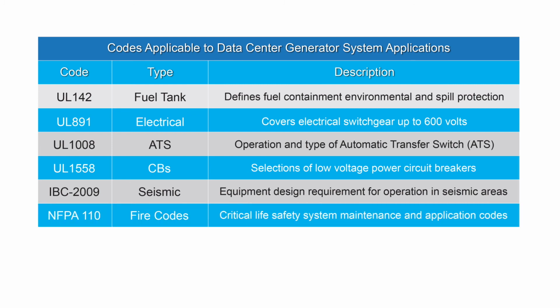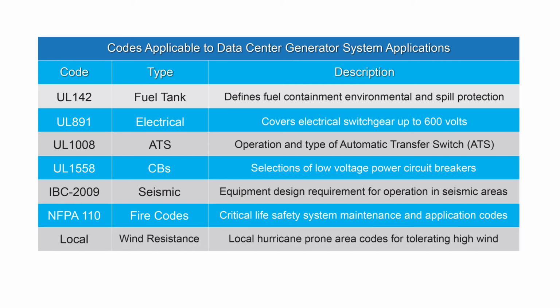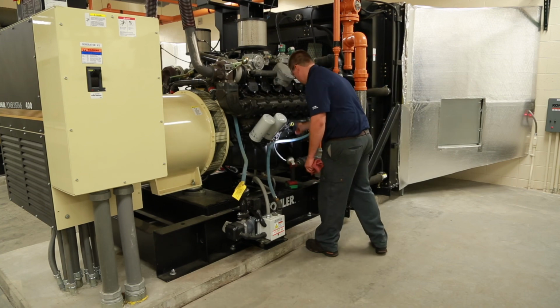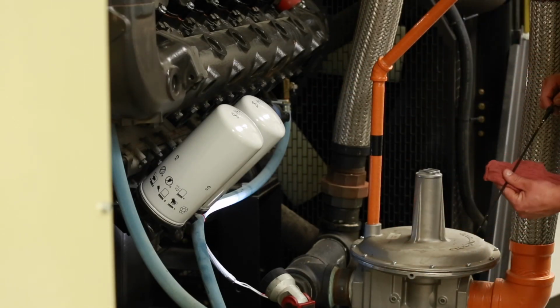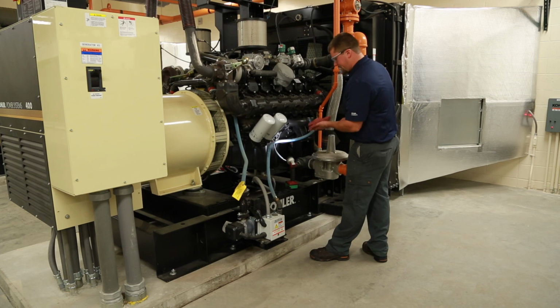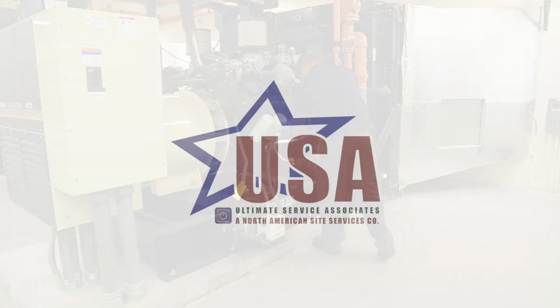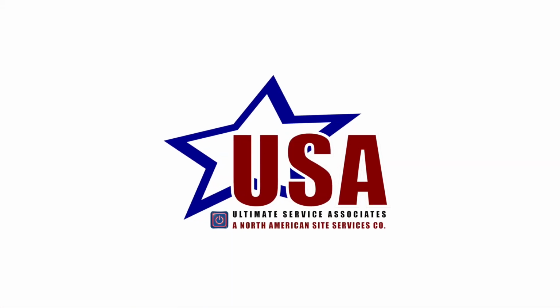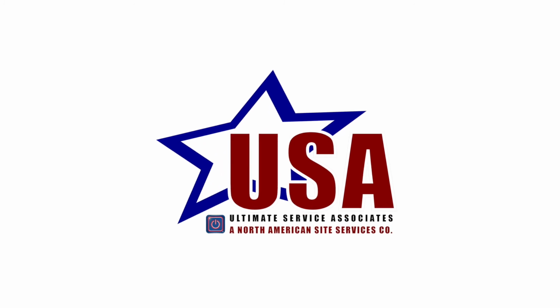Critical life safety installations are also subject to recommended maintenance projects as specified in National Fire Protection Association codes, such as NFPA 110. In hurricane-prone areas, outside installed generator systems may be required to sustain winds of up to 150 miles per hour. We can provide planned maintenance support that meets all applicable codes to ensure maximum reliability. We are ready to meet your standby power needs for any application, including data centers, critical to the functioning of a modern digital society.